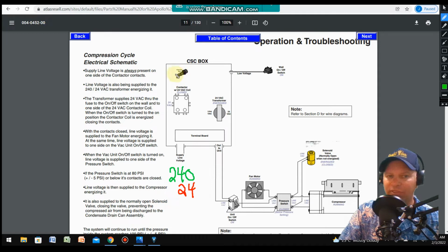And then we have a circuit protective device called a fuse. The fuse is there in order to protect against an overcurrent situation. And then we also have a wall on-off switch that is low voltage. It's a 24 volt switch, and this is for locating the switch somewhere further away from the compressor. This prevents you from having to run 240 volts through your wall to a switch somewhere else. So basically, we'll just dive right in here, and I'll try to illustrate how things are laid out.